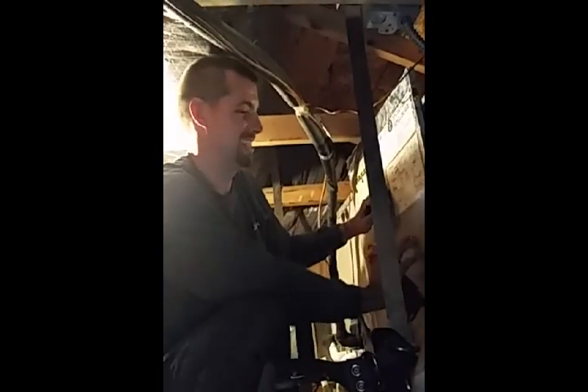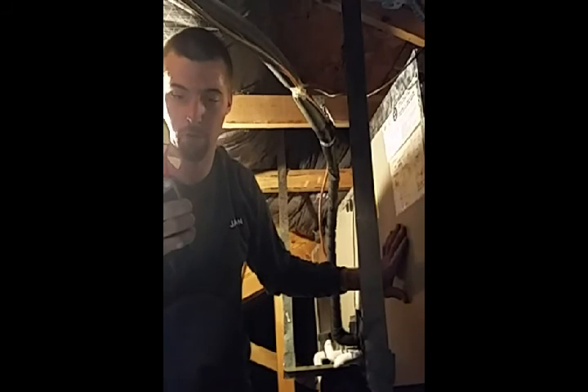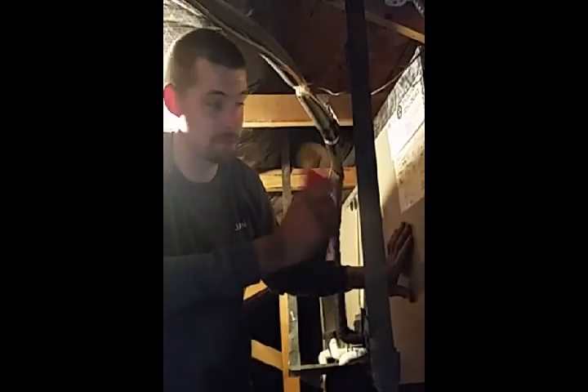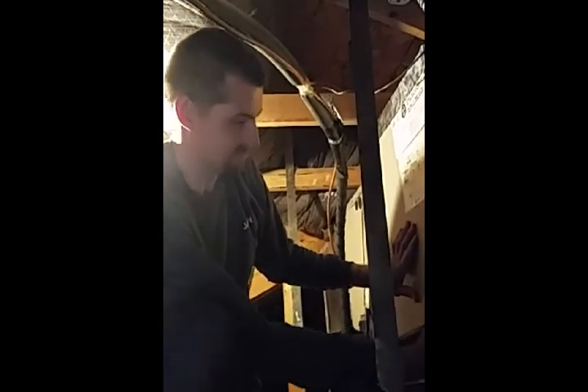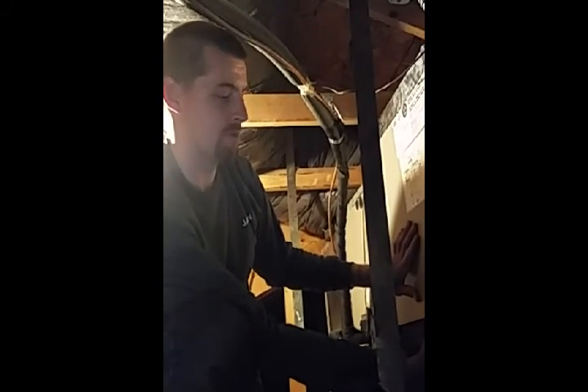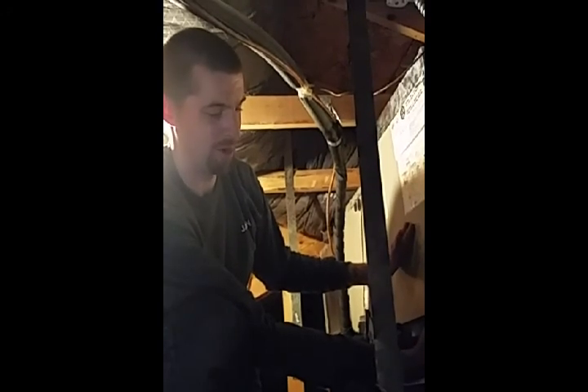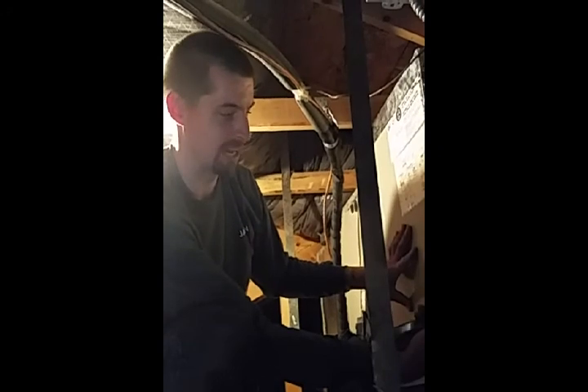Everything looks real good. I'm going to go ahead and put this panel in a way that when we go to start up, we can check our amp draws on our motor. Okay. So now I'm going to plug this back in. It'll come on. And basically what I want to do here is check the amp draw of the motor itself. This one is rated for 5.5 amps. So we will see what it is pulling. It's pulling right around 3.85 to 3.9, which is okay. So that's still in good shape.